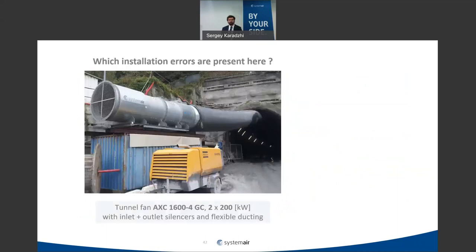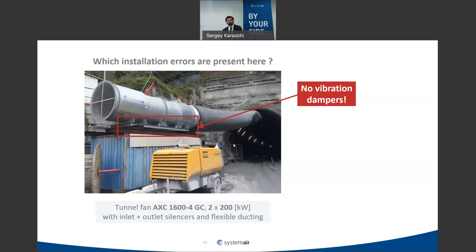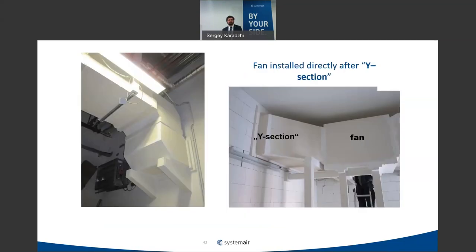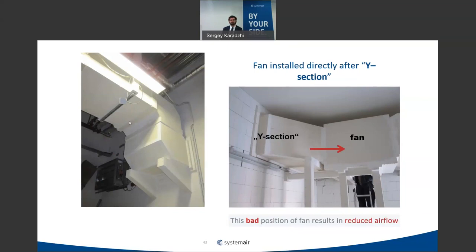Similarly, flexible connections going inside the duct due to too short a gap create additional avoidable losses and waste energy. A fan without any vibration dampers — as shown in another example — will distribute vibrations to the base structure, generating additional noise and eventually causing problems. Duct connections with sudden turns or abrupt geometry changes are also very bad and should be avoided.